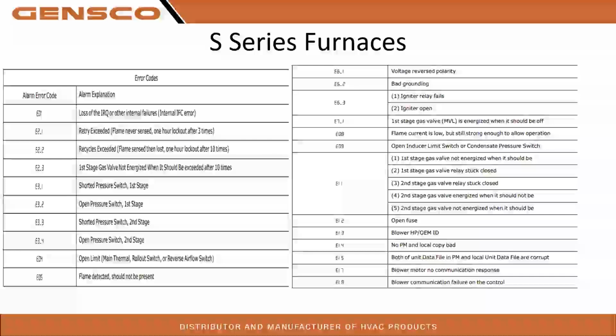So an example of that would be a pressure switch issue, right? Now instead of just giving you a 3 flash and saying you have a pressure switch issue, troubleshoot 1 or 3 of the pressure switches involved, we can actually say E3.2 for open pressure switch first stage, right? Or 3.3 for shorted pressure switch second stage. So we're giving you a direct call out of which pressure switch we're seeing an issue with. So much more informative. Not that the old system was bad, but this one's much more informative. Of course, with E6.3 and stuff like that, you're going to have igniter relay fails or igniter opens. So we get a lot of troubleshooting out of these newer furnaces than we did the older ones.